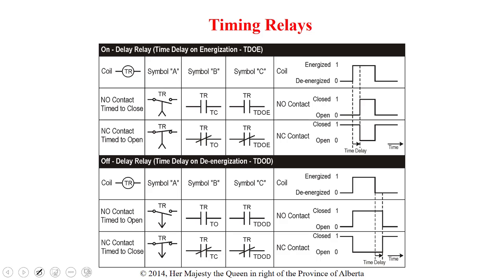So as we go into these reduced voltage starters, we're going to do a quick review of timing relays, so some symbols and so on. The symbol for a coil is right there. What we're going to look at first are on delay timers, or time delay on energization. That means we have a set of contacts that, after I energize the coil, are not going to change state immediately until after the given time has elapsed. So if I follow this little picture here, at this point in time the coil gets energized, and then for whatever means it gets de-energized right here.